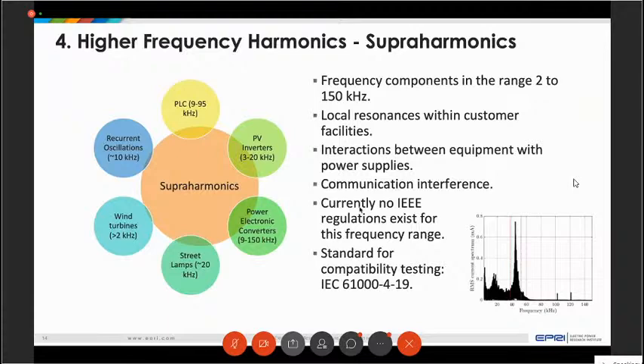Those switching frequencies can cause - we'll use the term in quotes - harmonics or noise on the system at those high switching frequencies and harmonics of those switching frequencies, and excite local resonances. We call this supraharmonics. That's kind of the new term for this - harmonics in the 2 to 150 kilohertz range.